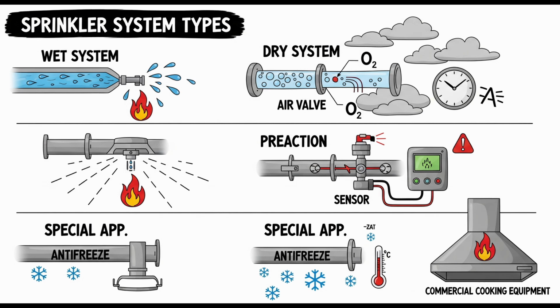The source also mentions a permitted air leakage rate, referencing another section for the specific value. We don't need the number, but what's the point? All right, Section 29.2.2 details the maximum acceptable rate of air leakage, which is a very low value. This ensures the system isn't losing pressure excessively. Constant significant leakage would cycle the air supply frequently and could indicate a problem like a loose fitting or a small crack somewhere in the piping. Checking the system's tightness, basically.